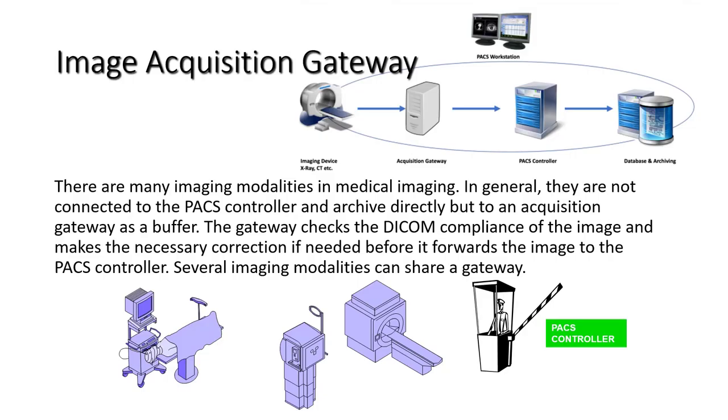There are many imaging modalities in medical imaging. In general, they are not connected to the PACS controller and archive directly but to an acquisition gateway as a buffer. The gateway checks the DICOM compliance of the image and makes necessary correction if needed before it forwards the image to the PACS controller. Several imaging modalities can share a gateway at a single time.